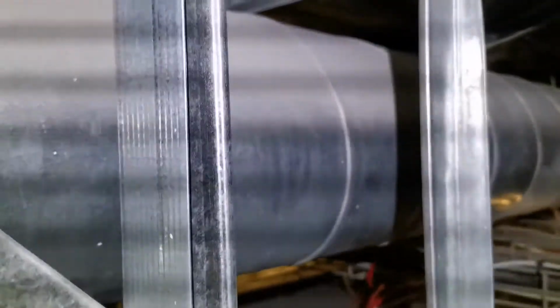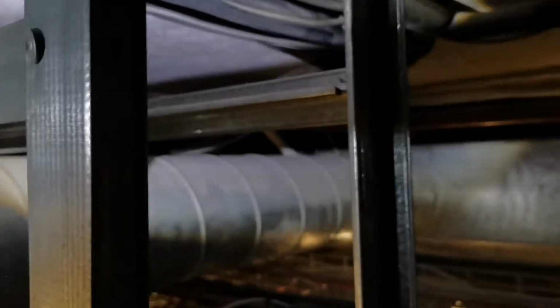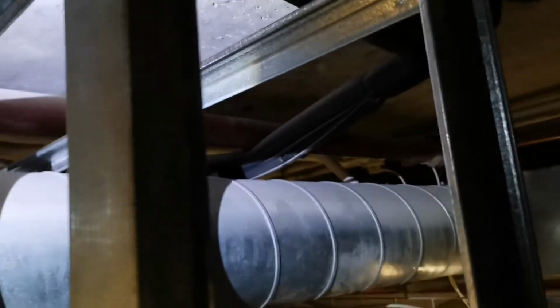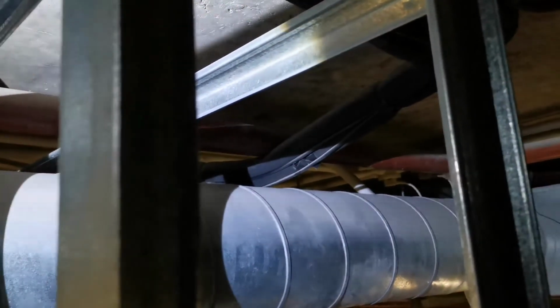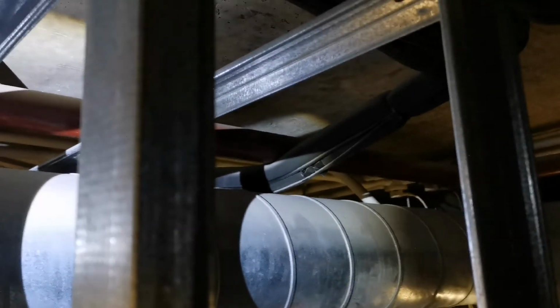And immediately after we had put the system on 40 bars, now it looks like it might be over there where the fire hose is rubbing against our refrigerant line. Certainly sounds like it's coming from that side. It might even be over there where that electrical conduit is. Alright, we're gonna open on the other side and then have a closer look. But yeah, man, that's what 40 bars does. So that's what the manufacturer recommends, and that's what we did, and we can hear the leak quite audible.